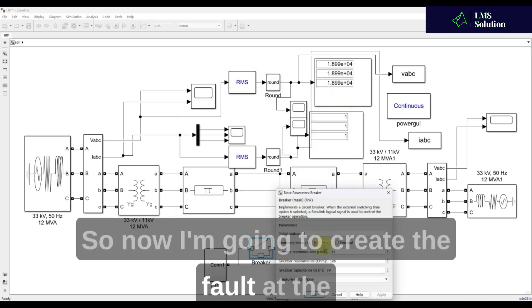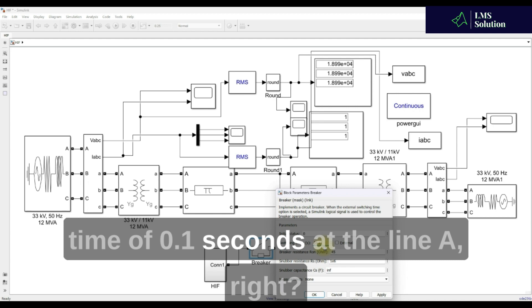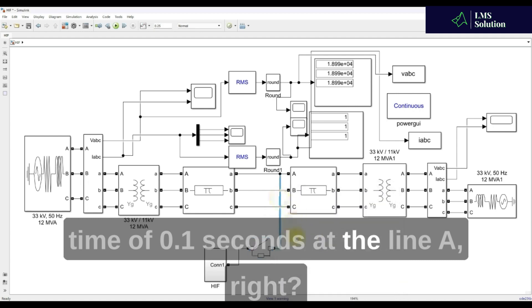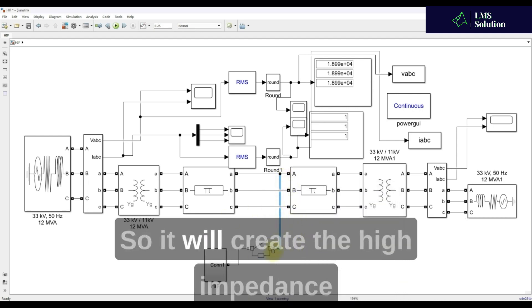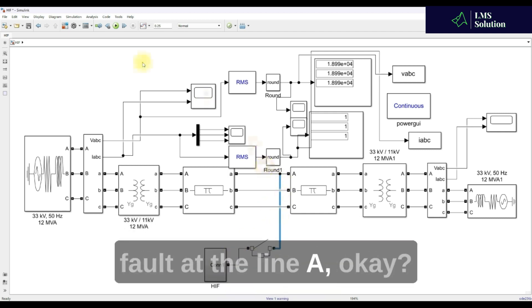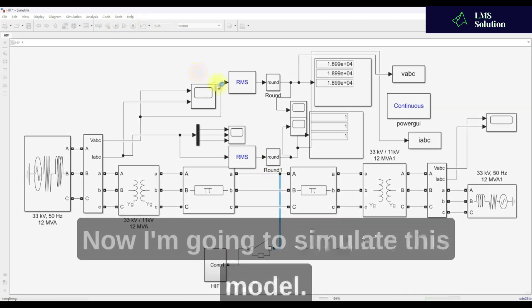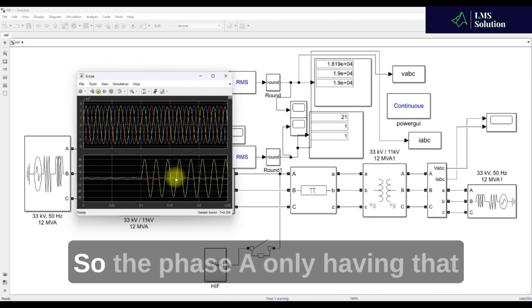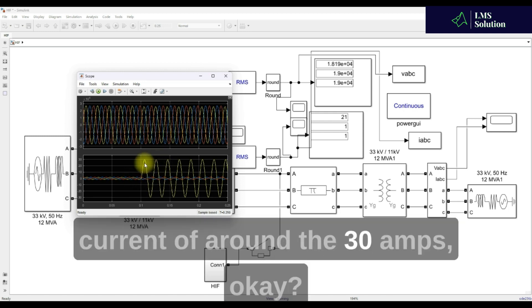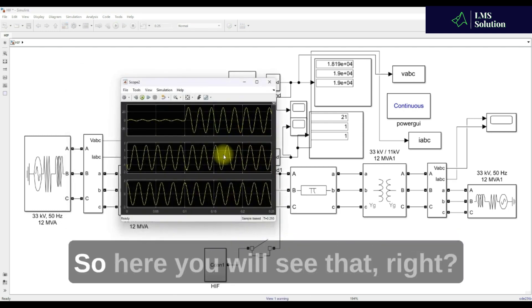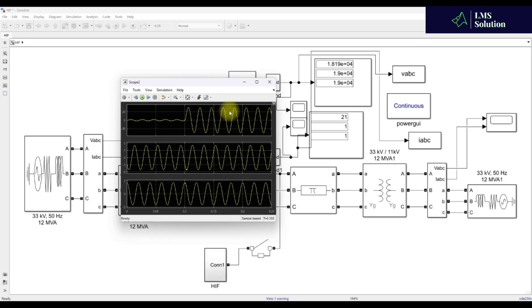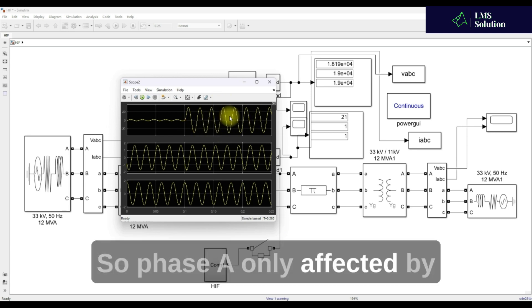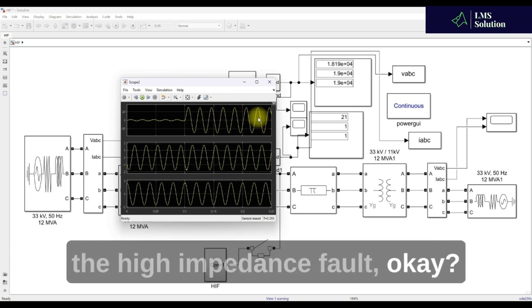Now I'm going to create the fault at 0.1 seconds on Line A, which will create a high impedance fault on Line A. After simulating, you can see that Phase A only has a current of around 30 amps, so Phase A is the only line affected by the high impedance fault.